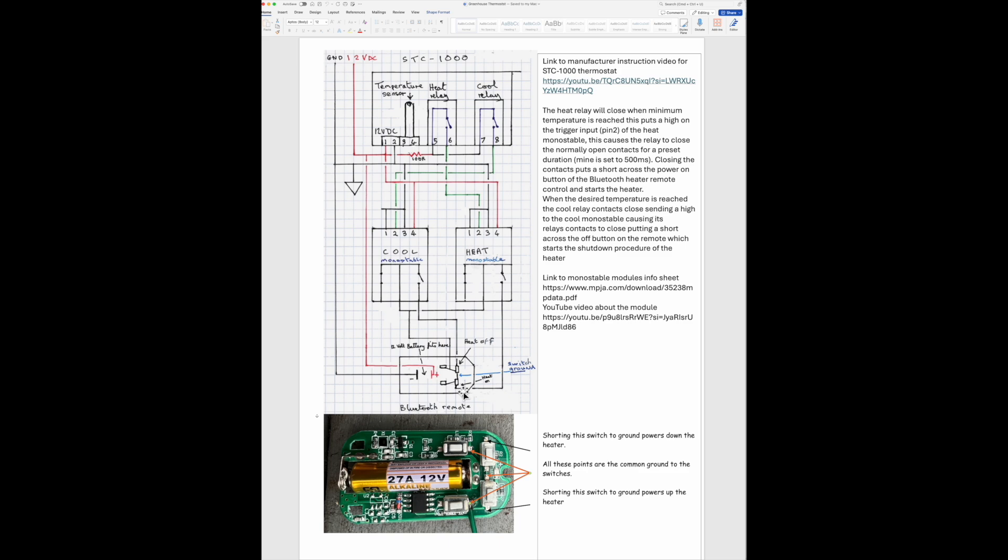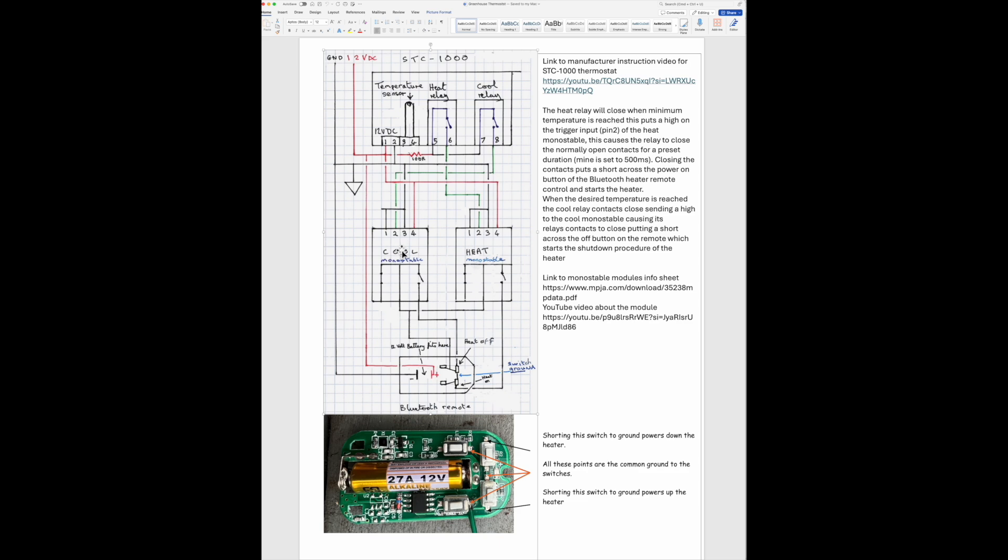Going back to the switch-off circuitry, the heat relay after about a one degree rise in temperature actually opens. Then when the temperature gets to the desired level, around about 11.5 degrees, this relay closes which then sends 12 volts to the input of the cool monostable, which does the same thing as the heat monostable. It produces a half second pulse, closing that relay and shorting out this button and initiating the cool down process. The fuel's cut off and the fan keeps blowing until the temperature of the combustion chamber reaches a safe level before the power is completely switched off.